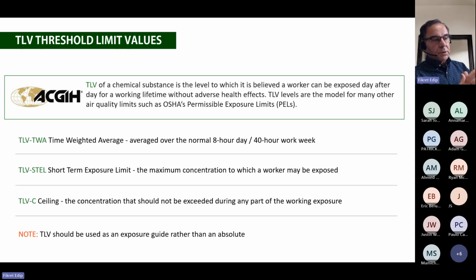When I say it is a guide, let me give you an example. Here in Ontario, we set our CO alarm set point to 25 ppm of CO as our low alarm. In some jurisdictions or in some states down south, they set it to 15 or to 10. Similar with other gases, like NO2. So this is why the ACGIH along with OSHA make recommendations. They give you the guideline, and then from there, the local authorities put the codes together. They set their own values.